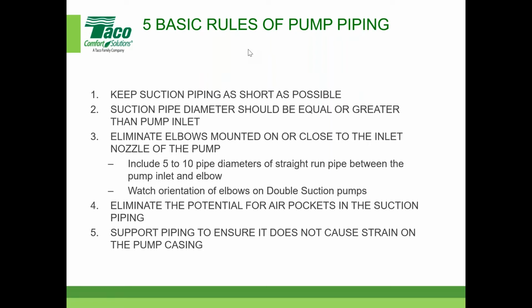Don't have a long run. Keep it as short as possible. Suction pipe diameter should be equal to or greater than the pump inlet. So if the pump inlet's 4 inches, don't go from 3-inch pipe up to 4. Have 4-inch or 6-inch going into that pump. Otherwise, you could create some turbulence. These HVAC hydronic pumps like smooth water coming in. They don't like it coming in swirling by any stretch.